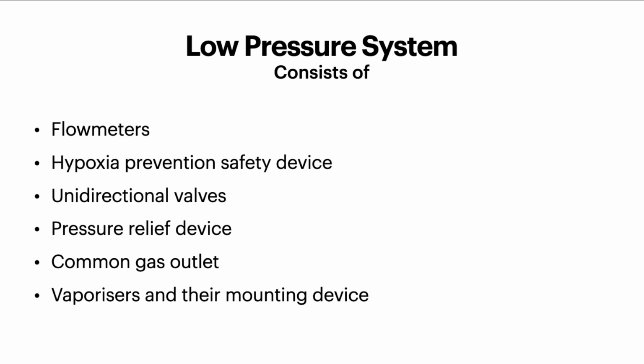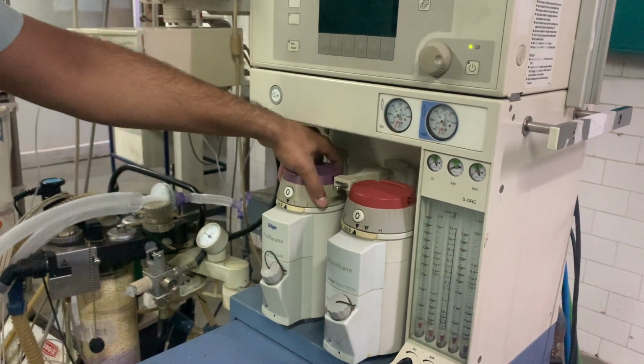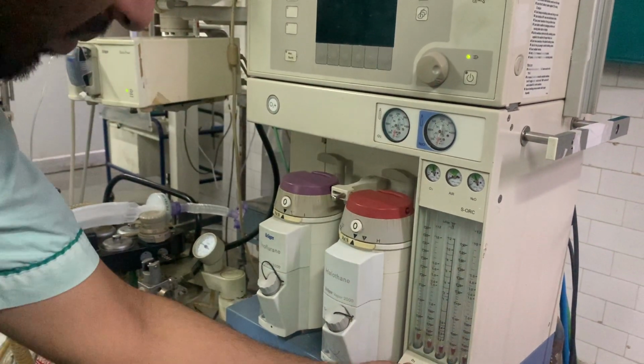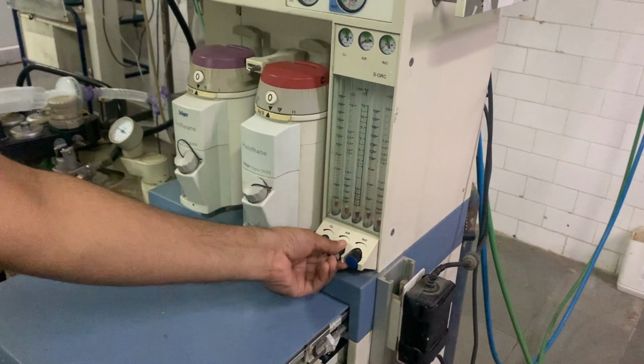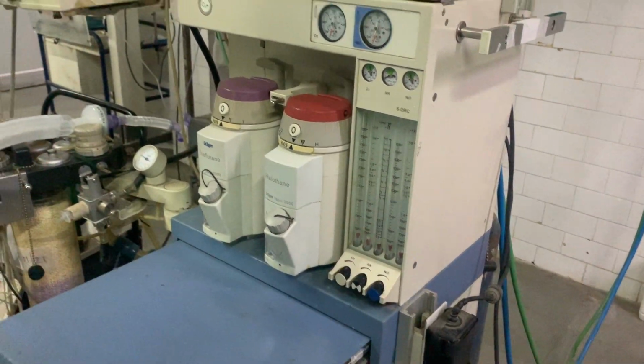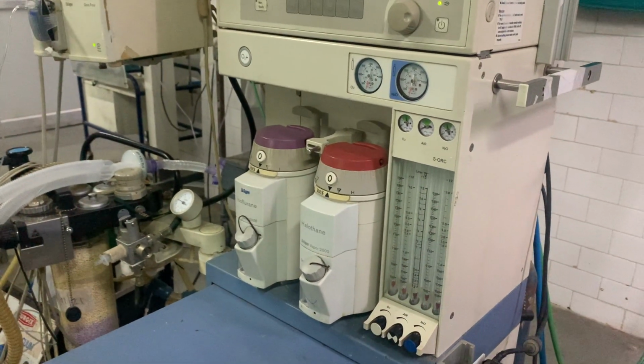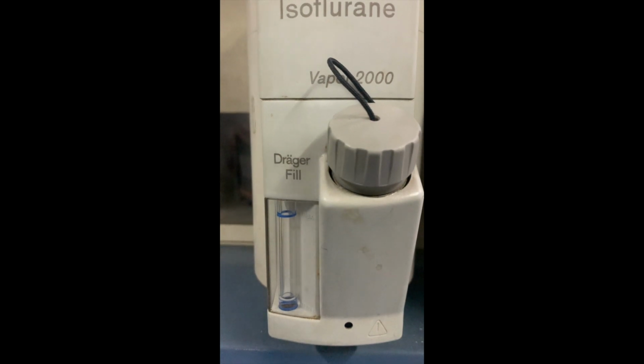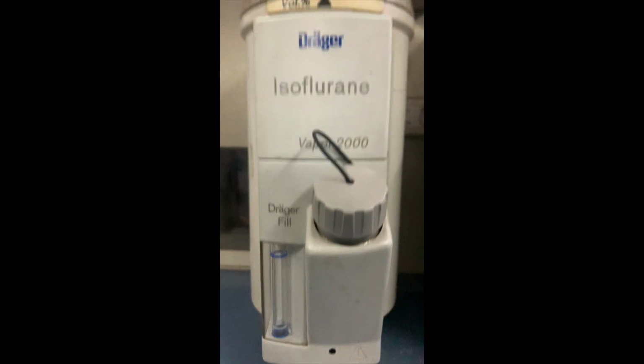The low pressure system consists of flow meters, hypoxia prevention safety device, unidirectional valves, pressure relief devices, common gas outlet, vaporizers and their mounting devices. Check the initial status of the low pressure system, making sure the flow control valves and all the vaporizers are turned off. Check the fill level and tighten the vaporizer's filler cap.